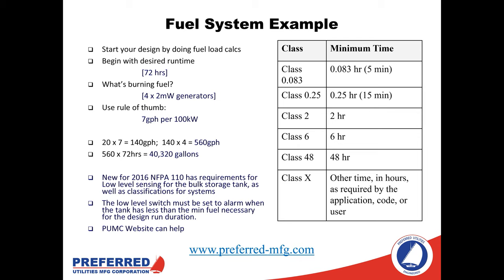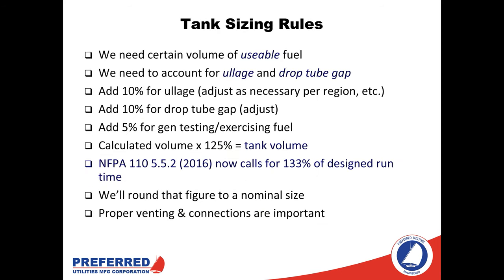Multiplying the burn rate by our total runtime, we get a raw number of 40,320 gallons. This is a raw number that needs adjustments. We have tools on our website, preferred-mfg.com, to help calculate how much fuel you need. We need to account for ullage — the headspace on the bulk storage tank that can't be filled with fuel — as well as drop tube gap, which is the fuel at the bottom that can't be pulled out because the drop tube for the suction side doesn't go all the way to the bottom.